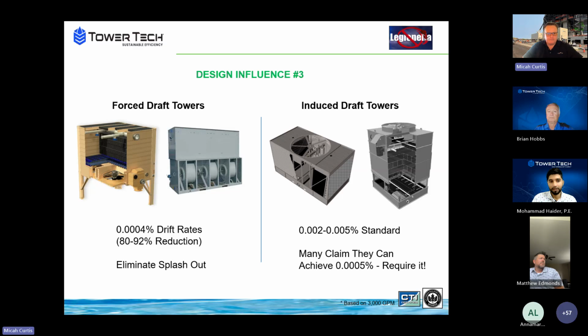Let's talk about that, Mohammed. Yeah, so keep in mind, when we're talking about drift, we're talking about chemically treated water, which in some facilities is very heavily chemically treated water, which could be harmful to the skin. So we're not just talking about Legionella strictly, we're talking about chemically treated water put into the surrounding environment. So you can have forced draft towers that have very, very low drift rates, and then we discussed the induced draft tower and their 0.002 to 0.005 drift rates. Now, one of the things you can do, especially with these induced draft towers, is that you can spec out an extra layer or different style of drift eliminators to potentially get a lower drift rate.